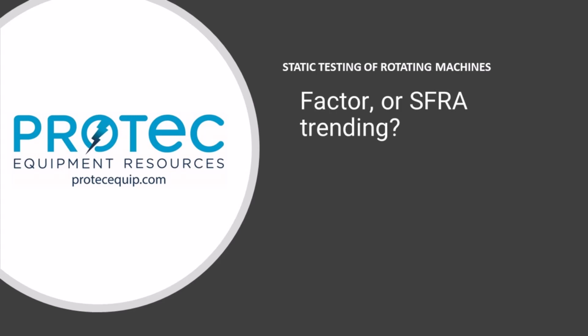SFRA is a very fascinating one because what SFRA does is inject signal in, signal out, over a band of frequencies. When we look at the mechanical structure of a device, it is made up of inductance, capacitance, and resistance. Over time, through vibration and so forth, if things are coming loose or jolting within the motor, it could change, for instance, distances between windings, which would affect capacitance. Loose connections could add resistance or change inductance. So the SFRA pattern is very fascinating, where it's an electrical test that quickly tells us if there are mechanical changes occurring within the motor.